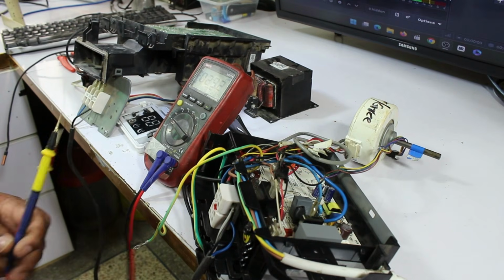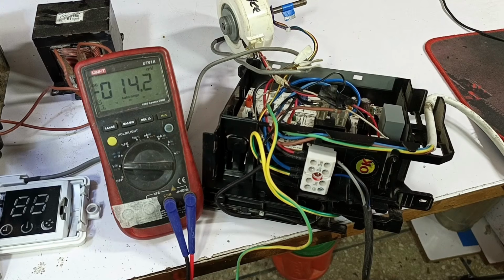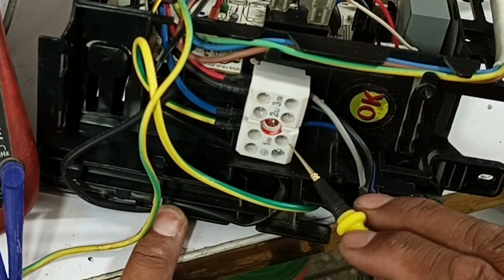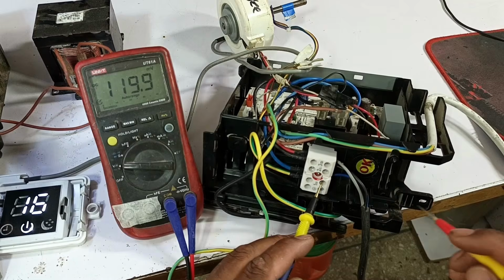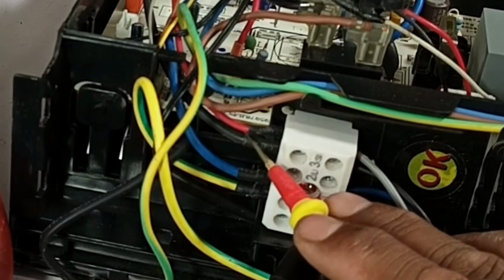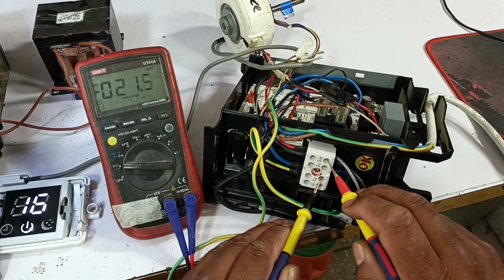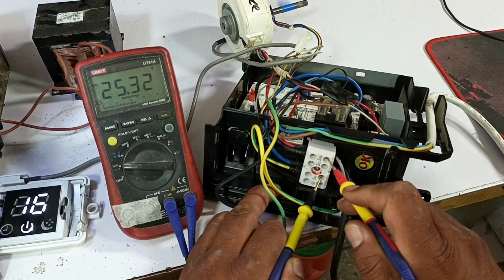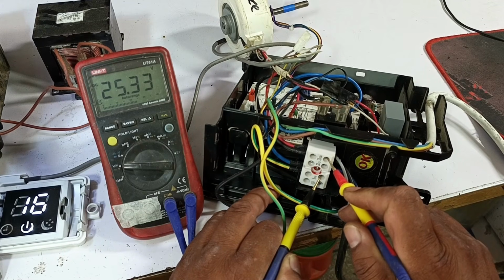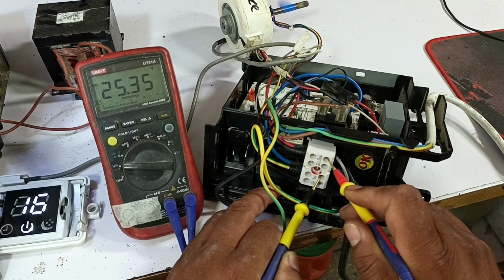Now, first of all, we will check the indoor. I will give it electric again. I turned on the electric, and this second pin is neutral. So I will place the black probe here, and I will check this red wire that we have. So here, as you can see, stable 25 DC volts are coming. So this means that the system is not working properly. It is not communicating. Its communication operating voltage is coming.